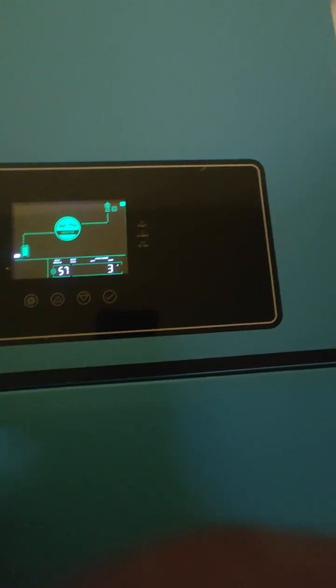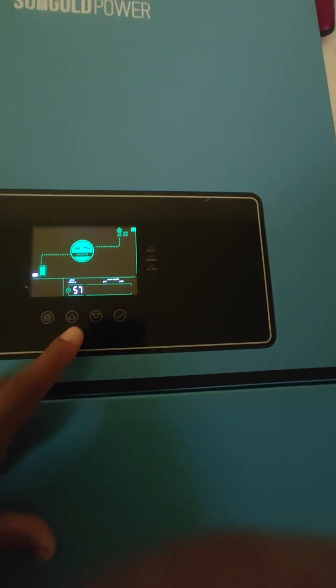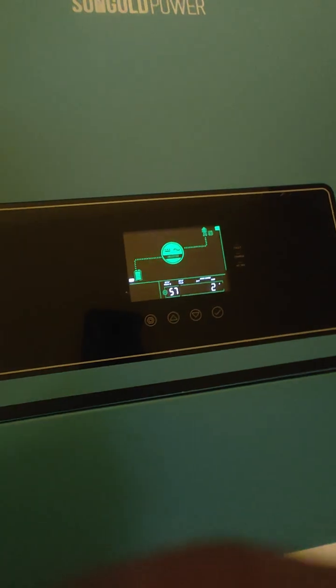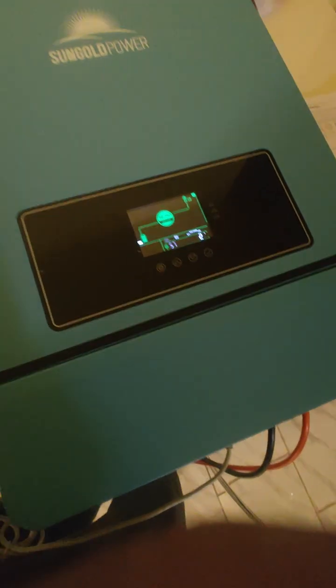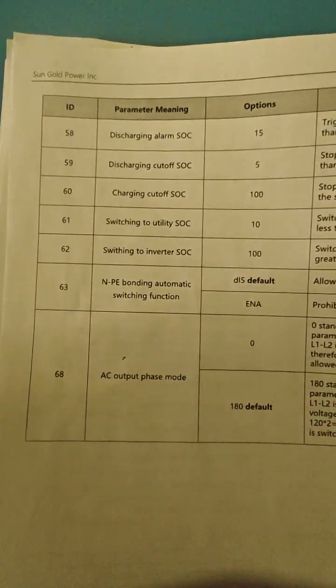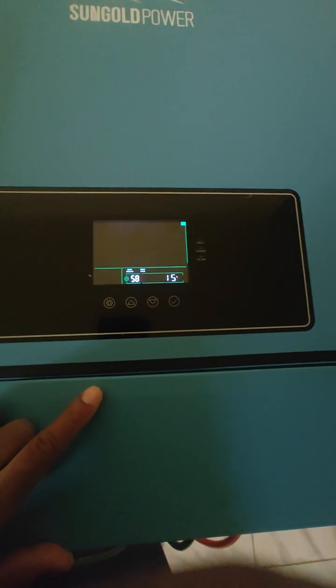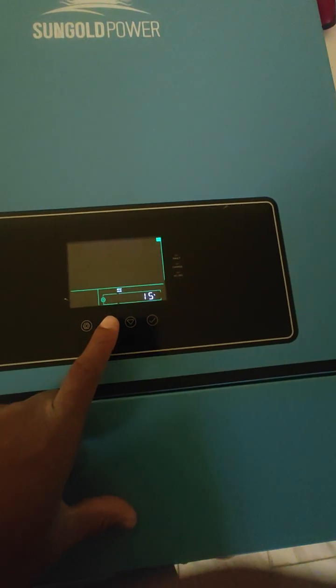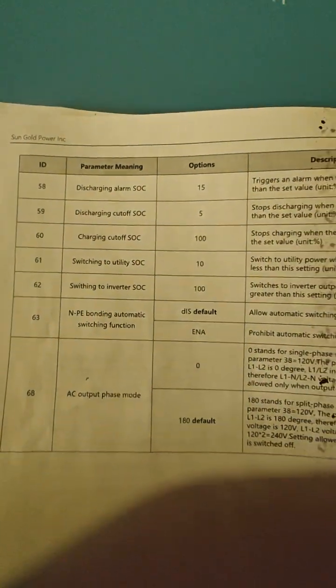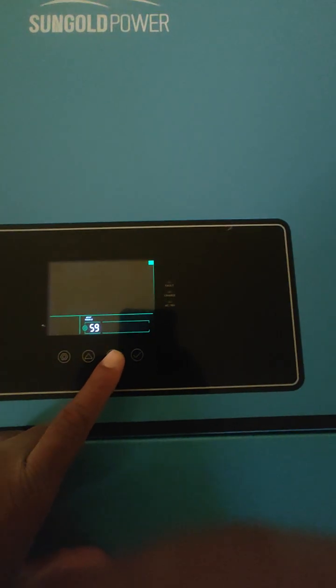57, stop charging current. Charging stops when the current is less than the set value, amps. So it says 3 amps here. The default looks to be 2. So we're going to change that down to 2. So we're going to go to 58. It's the discharging alarm state of charge. Let's see what that is. Set to 15, which is default. We're good with that. 59. The discharging cutoff state of charge. So we're going to set that down to 5 as well.